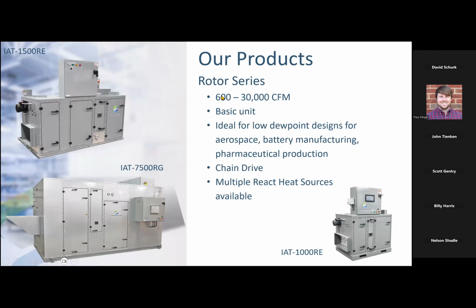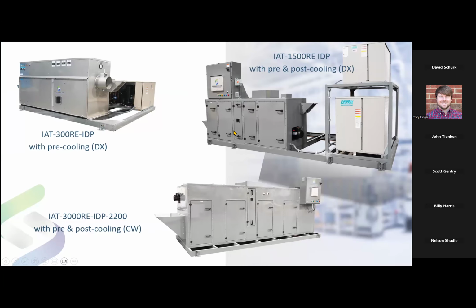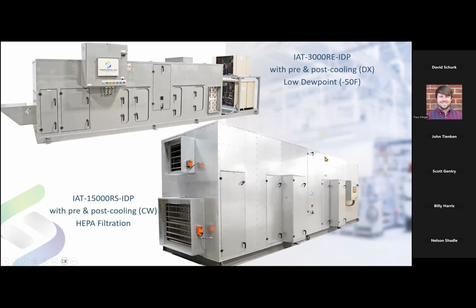And from there, 600 CFM and above, we go into what's called our rotor series. We go up through 30,000 CFM with these units, indoor, outdoor, can have pre-cooling and post-cooling and preheating and post-heating and HEPA filtration and bypasses and humidification. We can put air-cooled or water-cooled condensing units on them and give you a packaged solution, perhaps a DOAS, whatever the case might be. Sky's the limit, as big as you want. These are what we might provide in battery manufacturing plants, pumping out close to negative 80 degree dew point temperature air, as an example.